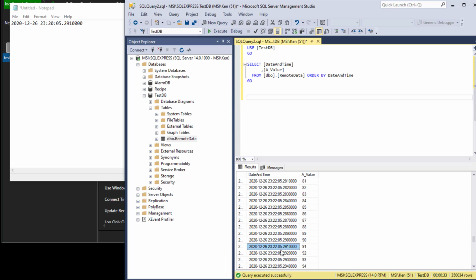There we are. And that was the value that we had at that time, at 91. And then we see the very next sample, during the store and forward functionality being buffering, we see the next value is at 92. So you can see there was no data loss during that temporary network failure. And of course, we have all the records going forward of that system.